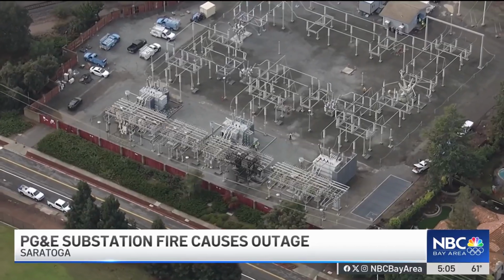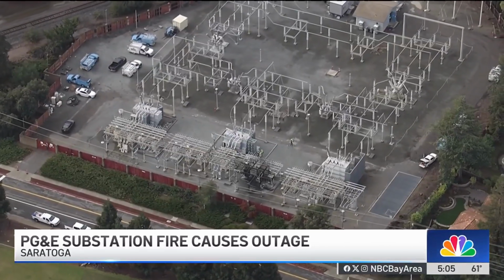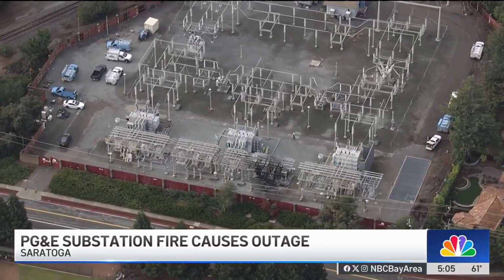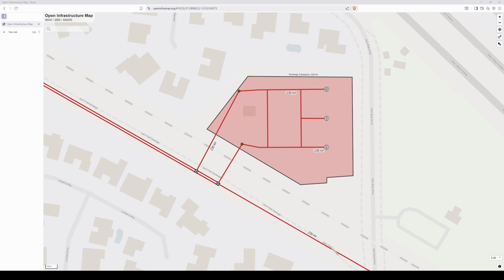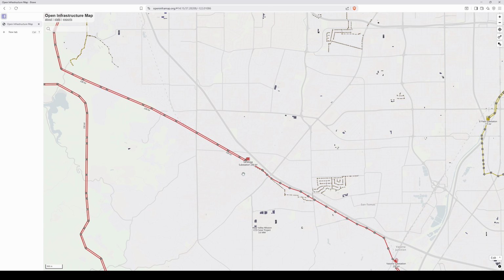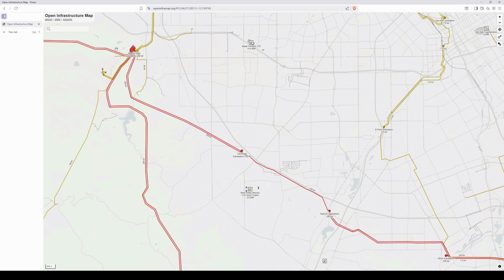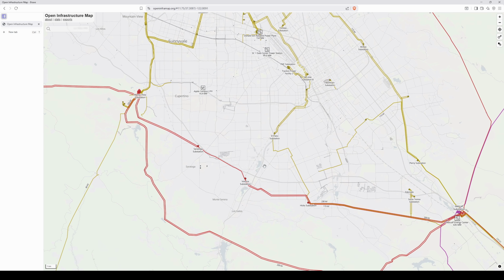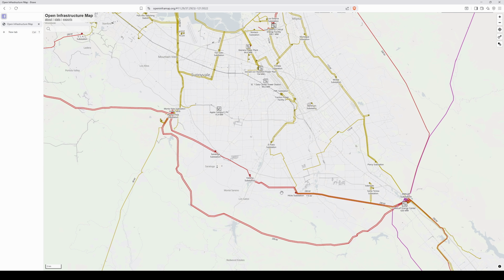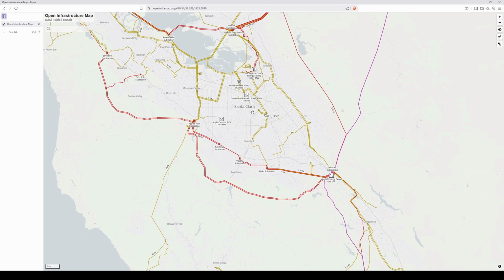I live in freezing cold England, so I can't just fly my drone over to take some video, so I'm relying on this low resolution video I found online, which looks like it was taken from a helicopter, courtesy of NBC Bay Area. At around 11 seconds in, we get our first glimpse of the substation, which, from consulting open infrastructure maps and some research, is a 230 kV substation, which is transmission voltage, between Monte Vista and Vasona 230 kV substations on that line. This line helps get bulk power in from Metcalf 500 kV substation, which is slightly to the east, into the San Jose area more efficiently, for it to be stepped down to a lower voltage and feed the residents and businesses here.